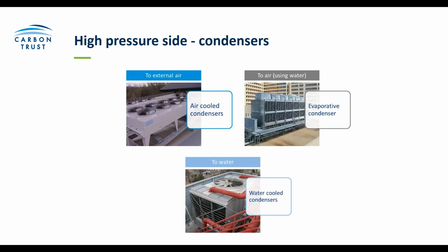In terms of the high pressure environment, this is where you'll see the condensers. So these all deposit heat to a local environment, and this is, as I say, often externally. So when air is cooled, the most common method is by simply blowing air, so air-cooled condensers, but you can also have the water-cooled type as well. Evaporative condensers are often for larger systems and use the evaporation of water to aid the cooling process.